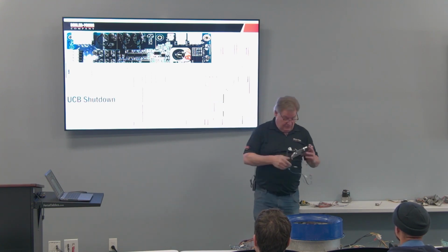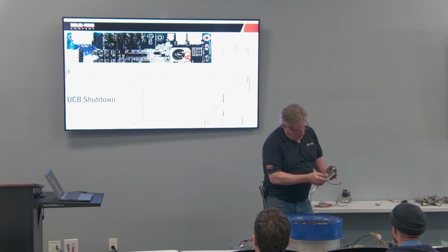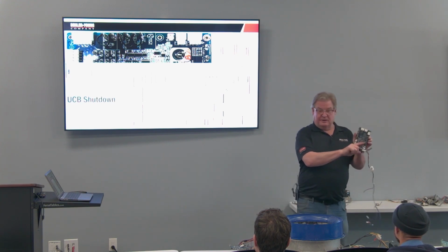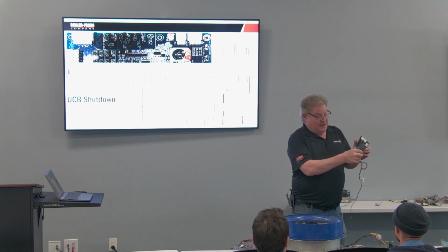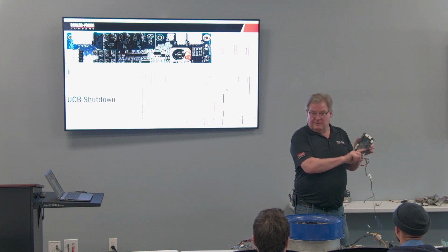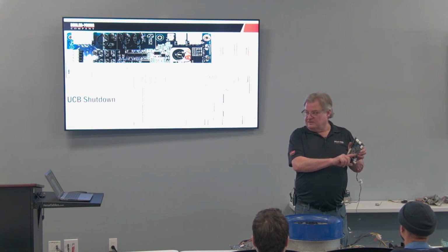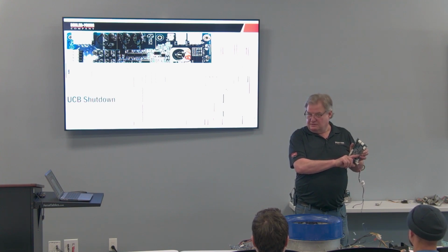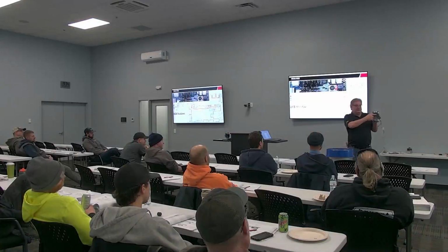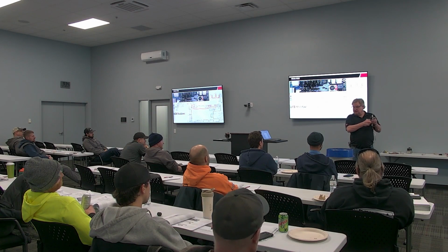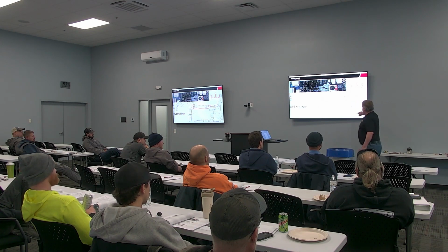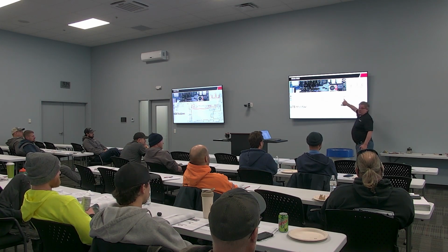And if I find on the board 24 out, this bottom one right here. If I pull this jumper, I still have 24 volts on that bottom terminal, right? Well, what's going to run my smoke detector? 24 volts. If I pick up 24 volts from the center of this board, guess what happens when my smoke detector opens? It kills it. So that bottom terminal is where you're going to power your smoke detector from. Everybody following that? One where it says 24 out?